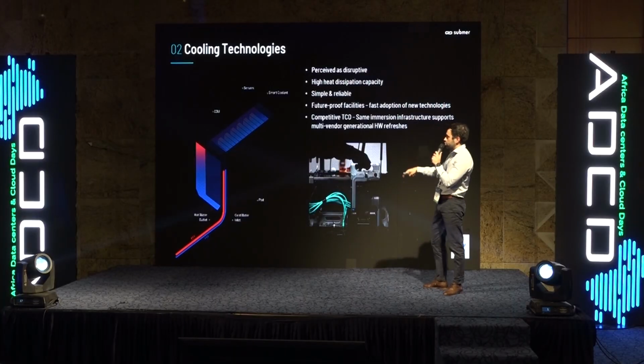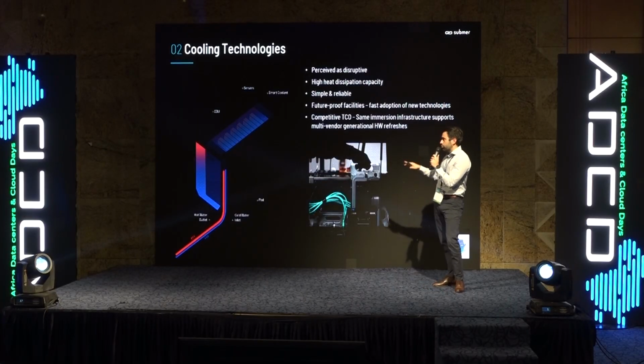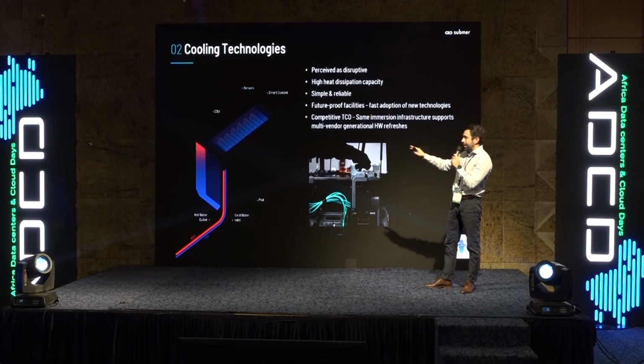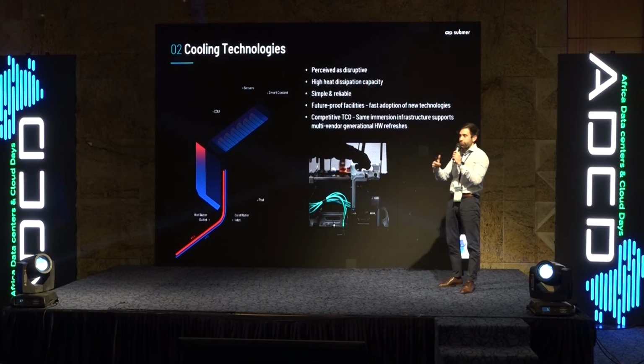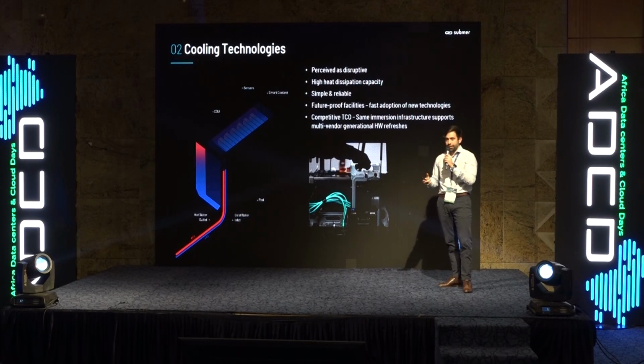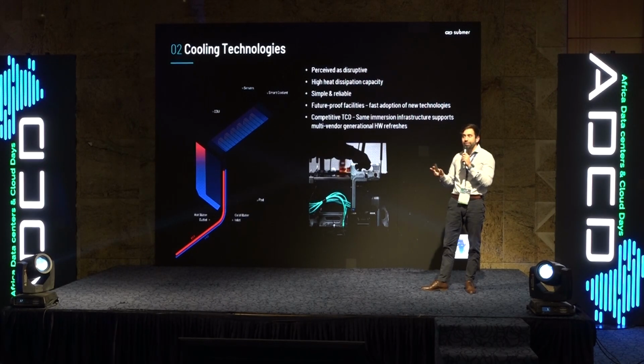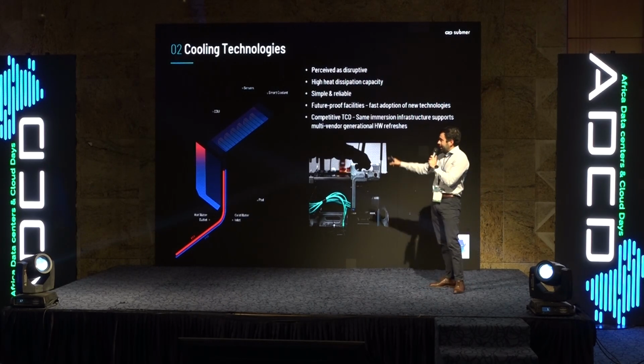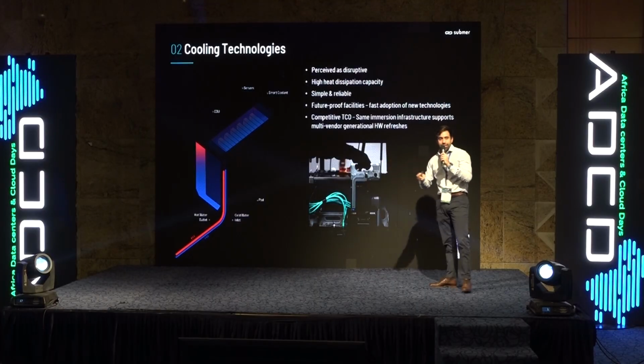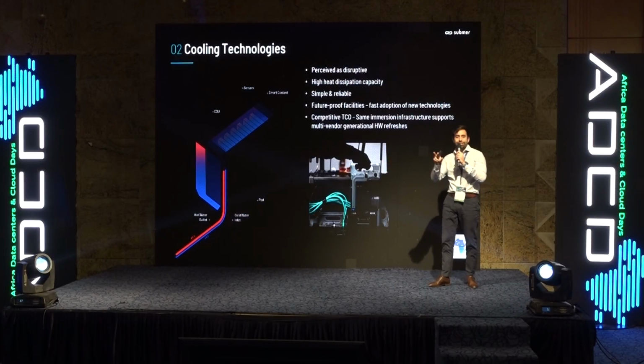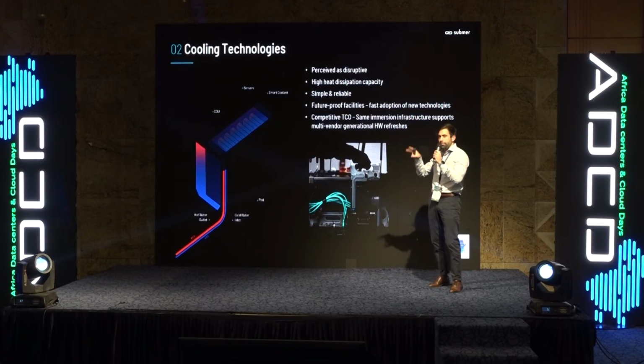Then you have single phase immersion cooling, which is what we do at Submer. Before explaining how it works, let's look at the main components. You have the tank where the fluid and servers sit, a dielectric fluid with a 15 year lifespan. Then you have the CDU, the cooling distribution unit, basically a heat exchanger with two pumps.